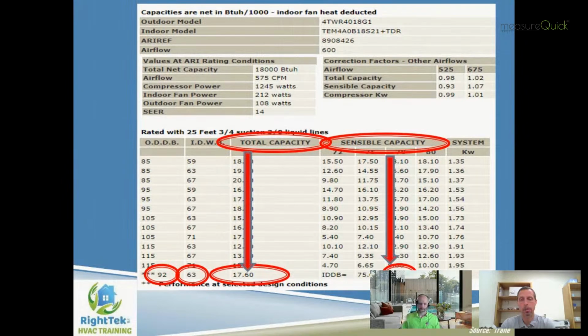So we need to go into this expanded performance data. All the major OEMs provide this in some way, shape, form, or fashion, and you dig into it to get the exact output capacity of that machine in cooling mode and in heating mode at the exact same conditions we ran our load at. So I always tell people we're trying to compare apples and apples here, and not two different sets of design numbers, apples and oranges. To me, that is one of the cardinal mistakes that a lot of folks who are not as familiar with Manual S and proper equipment sizing and selection tend to make. So you always want to make sure you dig into that.